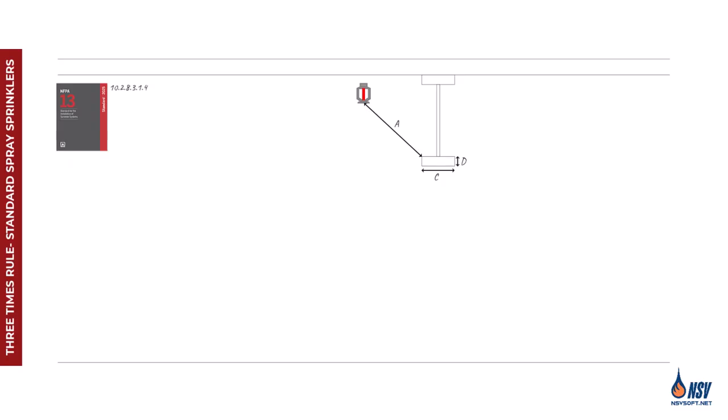For obstructions that allow water to pass on both sides, the sprinkler must be installed at a minimum distance equal to 3x the largest dimension of the obstruction.